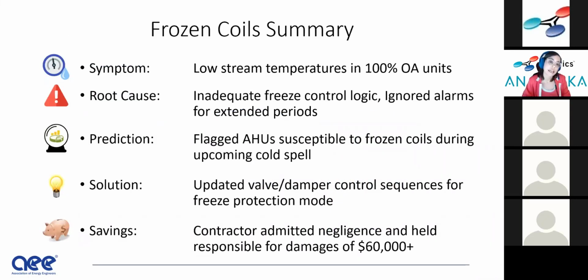In this case, we actually were asked to show this whole issue so that they could get money from the contractor. I say usually it's an entire partnership and we're not really a watchdog. In this case, we found low stream temperatures. There were 100% outdoor air units. There was inadequate freeze control logic. I won't go into all the freeze control logic now, but certain air handlers were flagged. They were susceptible to frozen coils. Sure enough, they froze. We suggested freeze protection control sequences and things like that. And the contractor admitted negligence here, and they were responsible for $60,000 of damages from frozen coils. The coils froze here. And you can imagine the cost of that.